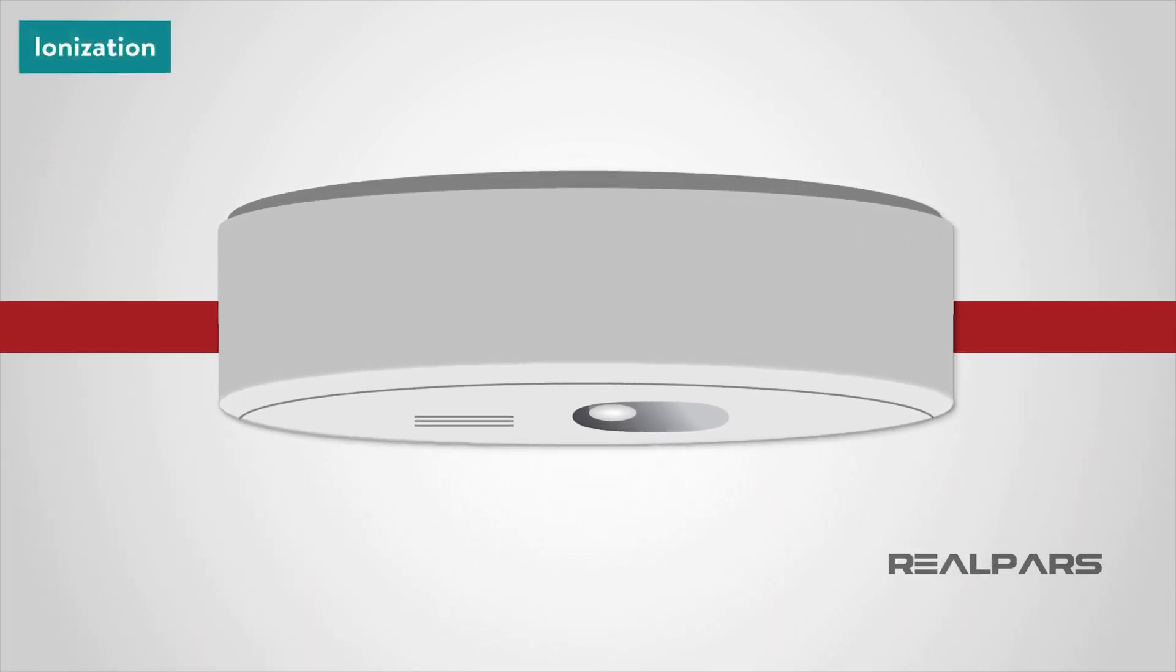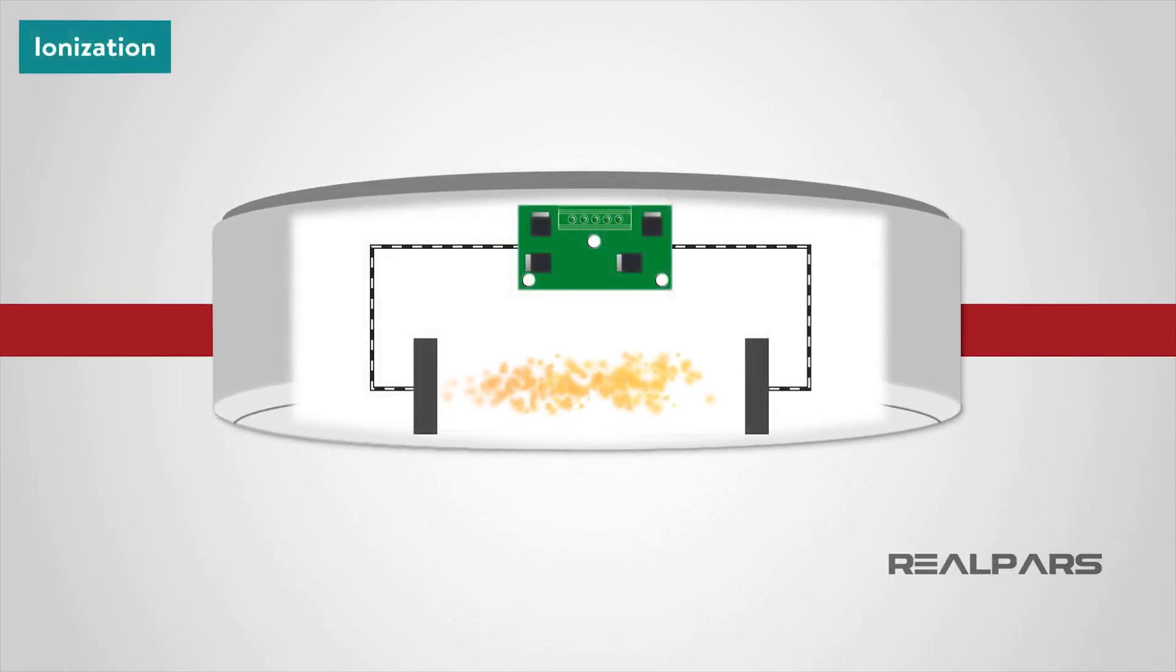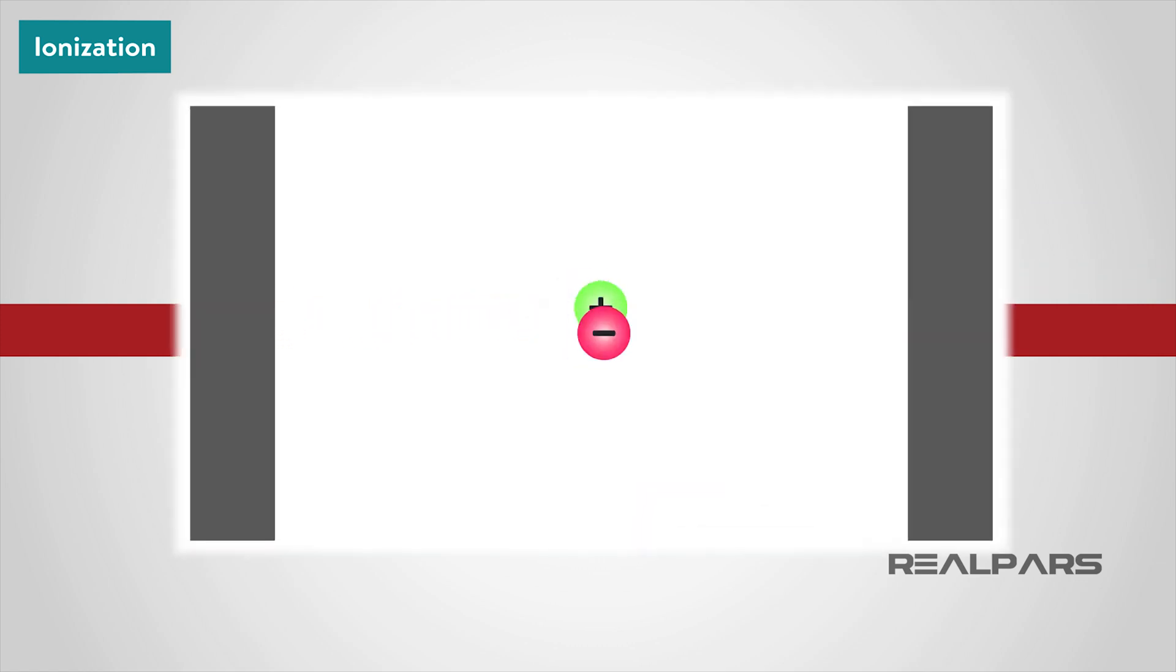An ionization smoke detector generally contains two chambers. The first is used as a reference to compensate for changes in ambient temperature, humidity, or pressure. The second chamber contains a radioactive source, usually alpha particle, which ionizes the air passing through the chamber where current flows between two electrodes.